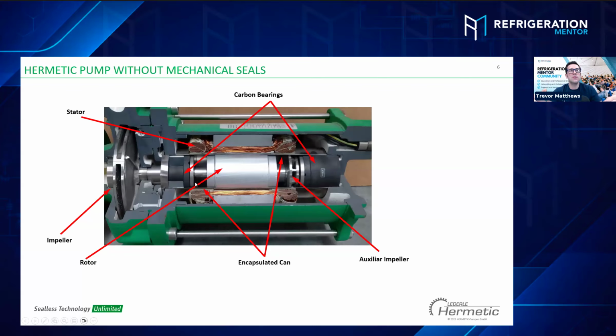Okay, so the liquid doesn't go over the windings itself, that's exactly the protection area. Okay, and when it goes through the crankshaft, is there any possible way that that can get plugged up? Because you always have a 10 psi differential. That's how we can move it back in, right, to cool the motor. Is there any possible way that that could get plugged up on a CO2 system? Because I'm pretty sure you mentioned to me on an ammonia system, oil could plug up that crankshaft.